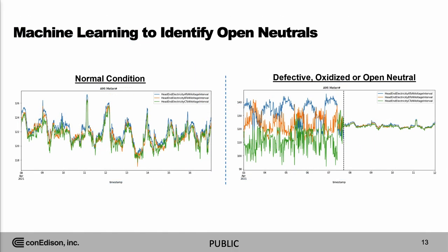We also used machine learning to look at the voltage waveform anomalies across the electric meters, and we developed a tool that tells us when we have an open neutral. An open neutral could lead to power quality issues at the meter. It could damage equipment, and it could cause electric shocks. This was a tool we developed with C3, and over the last year we detected 30 of these open neutrals.